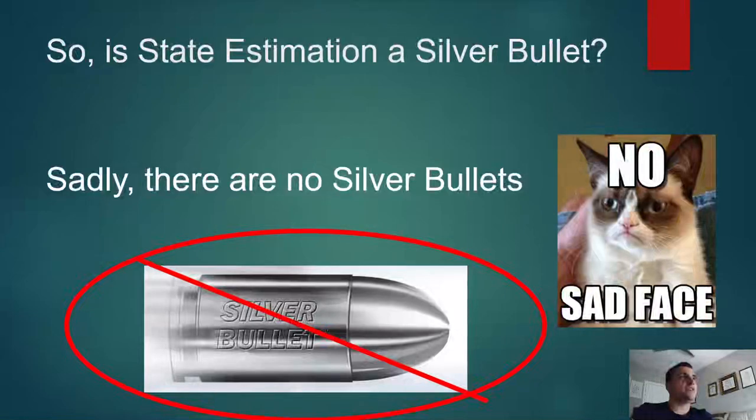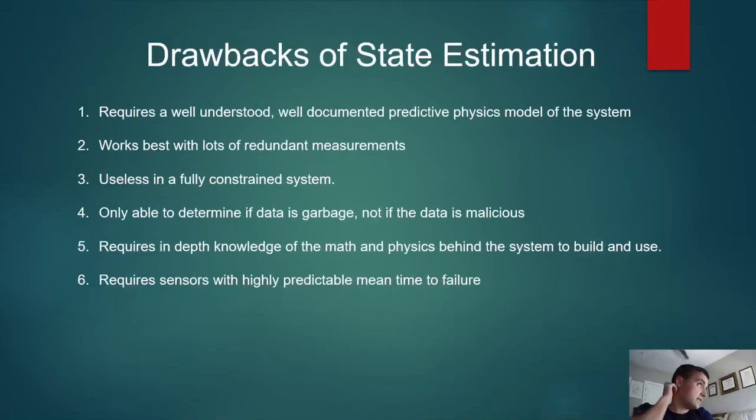Is state estimation a silver bullet? Of course not. We're all adults here. We know that there are no silver bullets. So it does have drawbacks. It requires a well-understood, documented physical model of the system, lots of redundant measurements, and you're only able to determine if the data is actually garbage. You're not actually able to determine if the data is malicious.